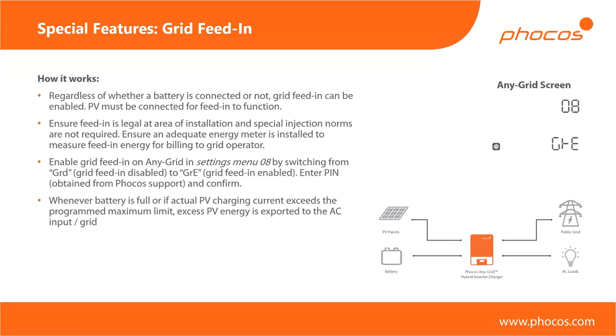The grid feed-in feature allows you to sell excess power to the grid when you have more power than needed to charge your battery or supply your loads. To enable it, go into settings menu number eight. A PIN is required — a four-digit number obtained from the support team — so that you don't activate grid feed-in accidentally, since many grid operators would be unhappy with unauthorized injection.